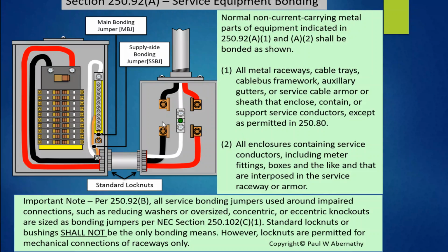So let's look at an example here. Here's our overhead service. This metal raceway, in this case we'll say it's rigid metal conduit, is threaded into a hub, one of the items listed in 250.92(B). Then it connects to this enclosure, which is connected through to the grounded conductor. You'll see this is perfectly acceptable in 250.142. We haven't gotten there yet, but you'll see that's a common application. And now all of this enclosure, everything's tied together.